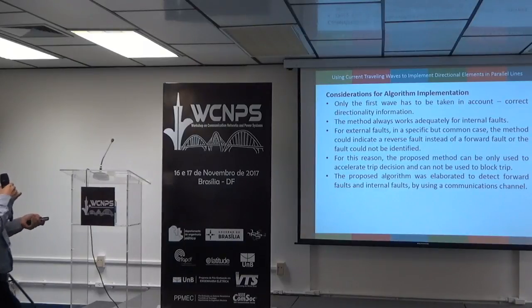The method always works adequately for internal faults. Internal faults, it will work well always. For external faults, in specific but common cases, the parallel lines, it's common to have the same lengths or double circuits, in the case specifically in double circuits. The method could indicate a reverse fault instead of a forward fault, or the fault could not be identified.